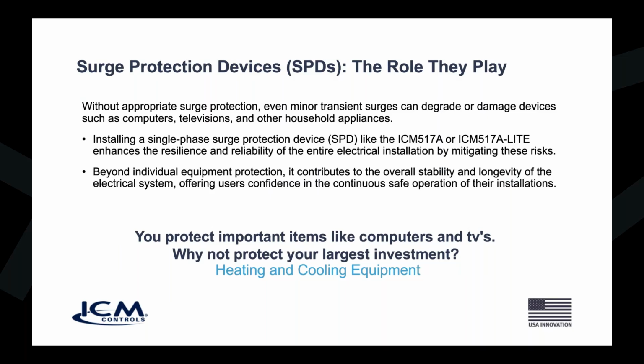All right, so without any appropriate surge protection, even minor transient surges can degrade or damage equipment, things like computers, television, household appliances, and those expensive electronic boards that are in your HVAC equipment or heat pumps or other devices, inverters, things like that. Installing a single-phase surge protection device, an SPD, like the ICM 517A or the new ICM 517A Lite, will enhance the resilience and reliability of that entire electrical installation by, of course, mitigating these risks, okay? So beyond just individual equipment protection, the surge protection also creates a more stable environment for the electrical system, giving you the confidence for continuous safe operation of your equipment.